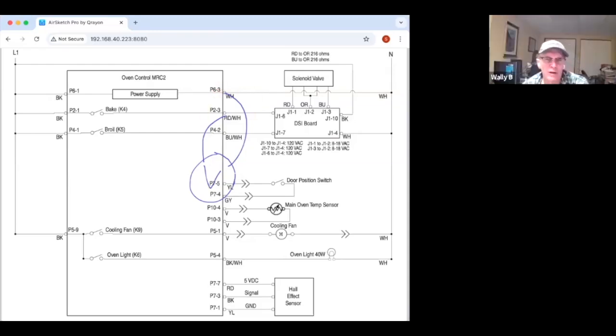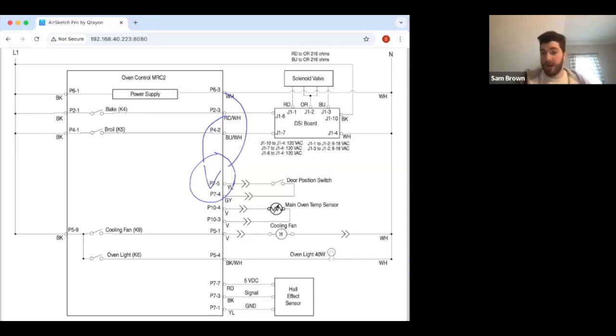Now that we know what we know, why wouldn't the initial procedure be to make sure that the oven control is sending the signal to the DSI board? All the stuff I went through about the DSI board was to make sure we understand how it works, because you need to understand how it works to know what your tests mean, to know what the behavior of the machine means. But yes, the way you test this is very simple when you understand how it works - it's just doing this measurement. This would be the first thing you do: if it's cutting out after 20 or 30 seconds, I should see if the voltage from the main board is cutting out.